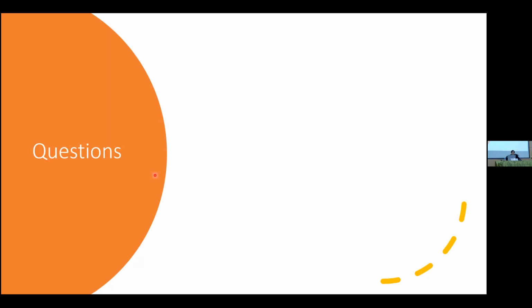Yeah, so that's, again, what we're talking about. I think the P-wall is probably like 0.25% to maybe 0.5%, and taking those into account is important. So I do think the new version has a little bit better mechanism. So instead of doing a cross calibration where you would say, here's my Roos one versus a Markus chamber, basically kind of the same mechanism, right? So here, for your reference chamber, do you have a calibration lab that's here in Thailand that you send it to?